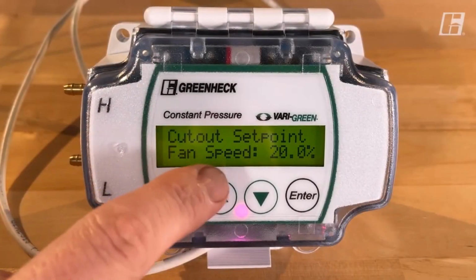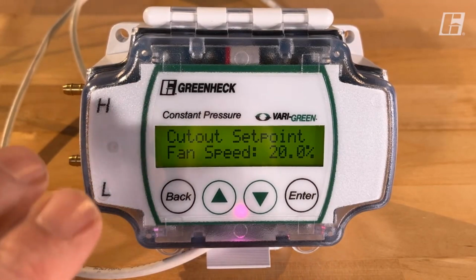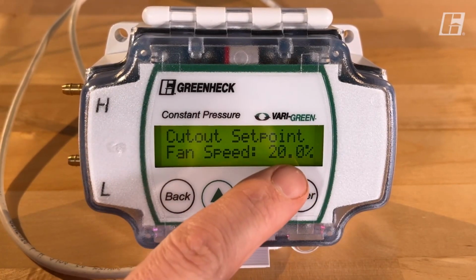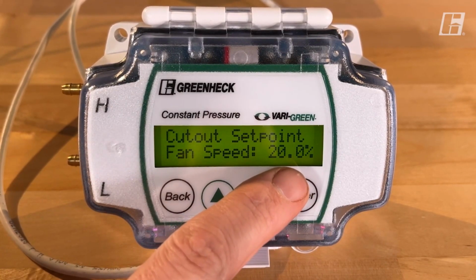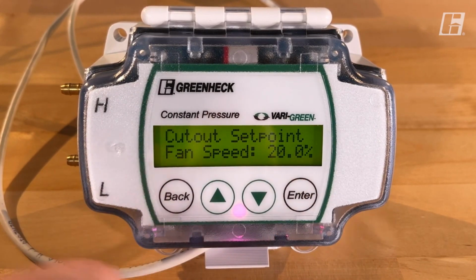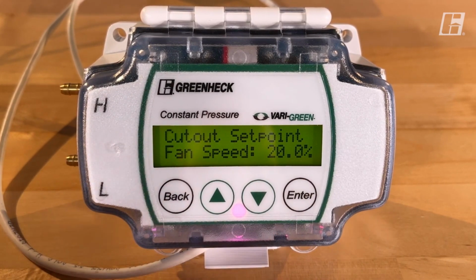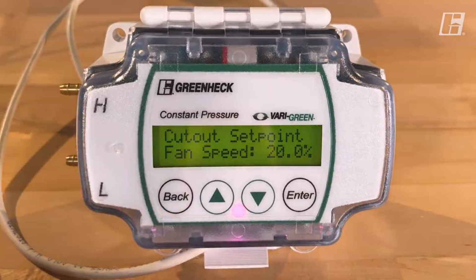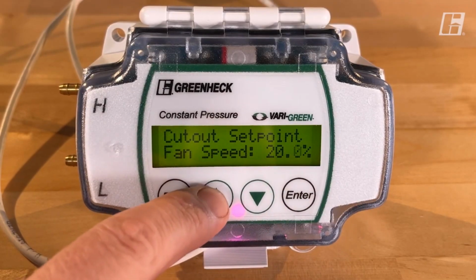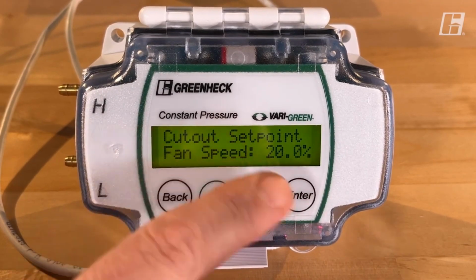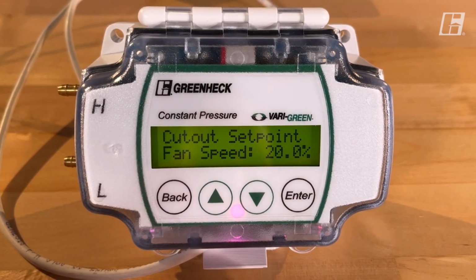Cutout, this parameter is the set point when the motor goes below this value, below 2 volts or below 20%, that this control says there's no demand on the system. I'm going to go ahead and shut down the fan. So you can set that to 20, 21, wherever you need to be. From the factory, we're at 20%.